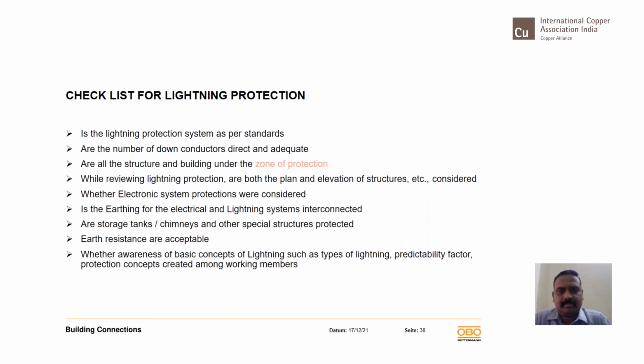Then, considering electronic system protection, check whether the earthing for the electrical and lightning protection systems are interconnected or not. If there are any storage tanks or chimneys, you'll have to follow OISD or NFPA standards, whichever applies as per the guideline of the client. And earthing resistance should be acceptable, and many of you have answered this. 92% was the correct answer. The value should be less than 10 ohms.